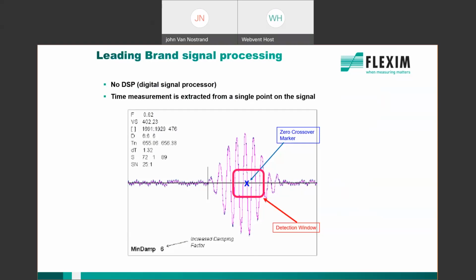So if there are 100 digital marks that are sent and 50 are received, the math is easy enough, 50% signal strength. And sometimes that digital mark can move based on the process conditions, like maybe the temperature of the transducer, for example, and it can move outside of that detection window, meaning that the signal is lost. Now you have a detection fault or signal loss or a red light or some other means to indicate that you've lost signal. The signal may still be there, but the meter just can't see it.